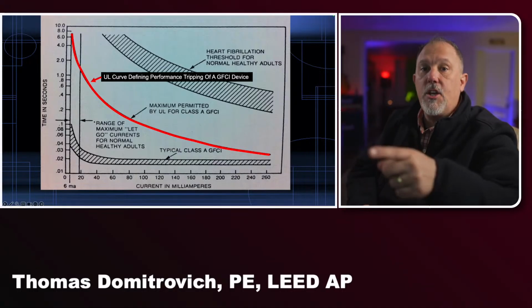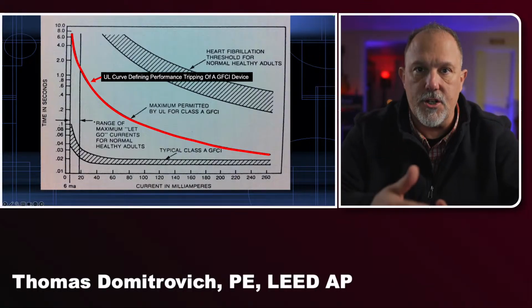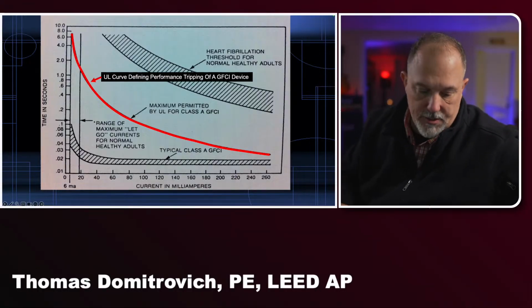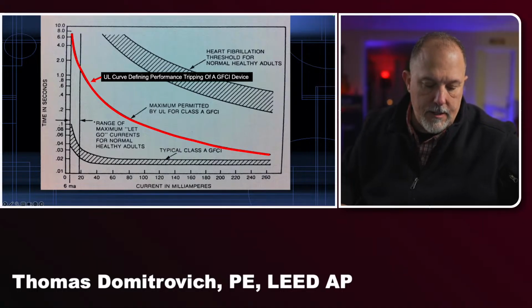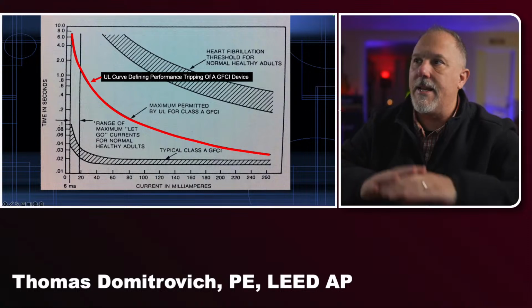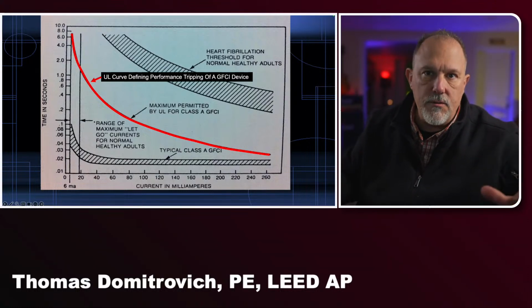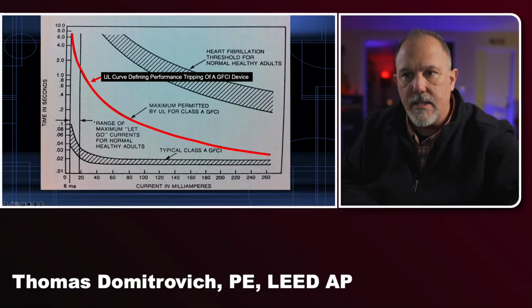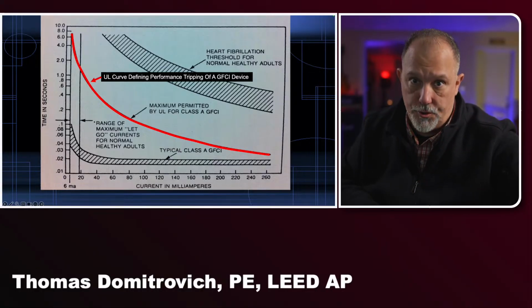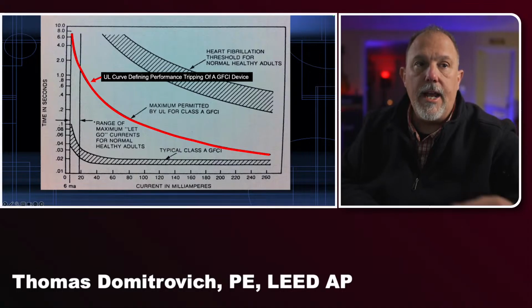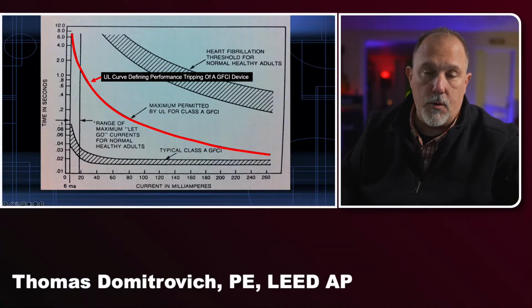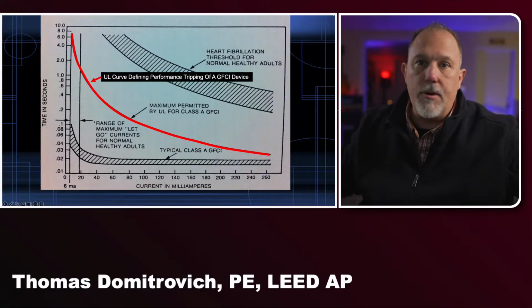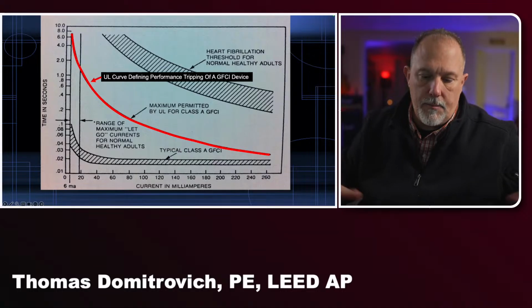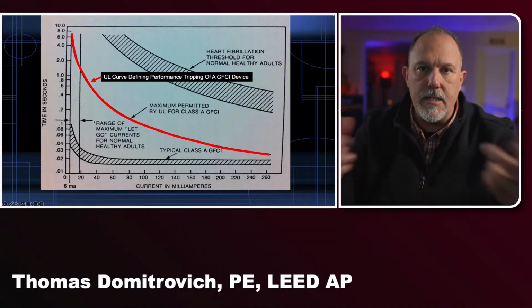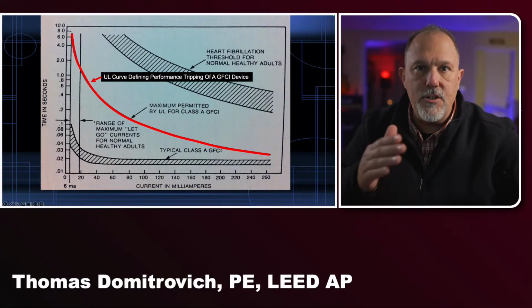So what's happening because of these leakage currents, and a lot of the leakage currents are temporary in nature. So when we design circuits, I try to tell my message to anybody out there who's designing stuff, if you're going to filter anything out, don't take it to ground, take it to a neutral. And the argument on some of the appliances is there's not a requirement to pull a neutral to the appliance. And if you don't have that neutral there and you have no use for it, when you start to filter things out, where do you filter them to? You filter them to ground. And they build a ground plane inside there and they put their capacitive coupling and all that good stuff over to ground. Well, that is ungood.